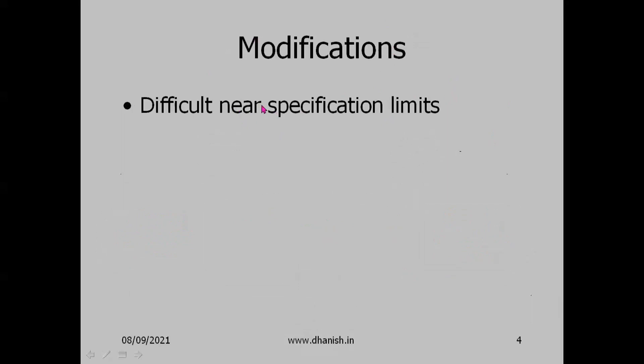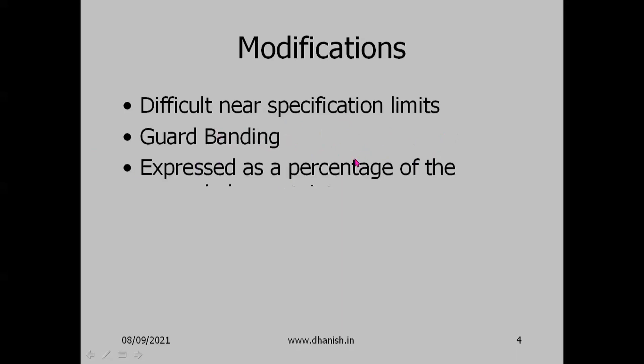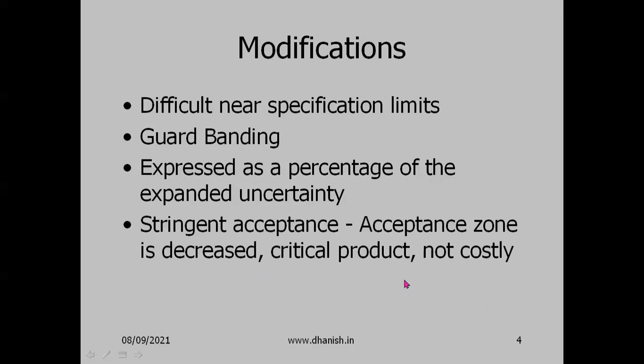Modifications were suggested because near the specification limits, there is a possibility that a bad product will be accepted or a good product will be rejected. Which is more dangerous depends on the nature and criticality of the product. This led to the concept of guard banding — the guard band is expressed as a percentage of the expanded uncertainty U, and the acceptance zone is modified accordingly.